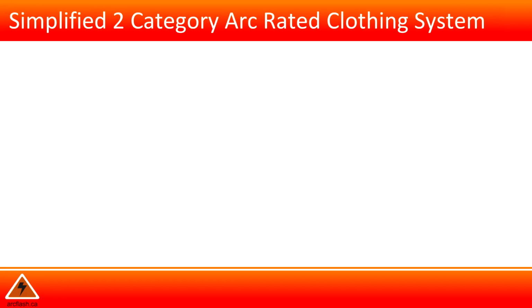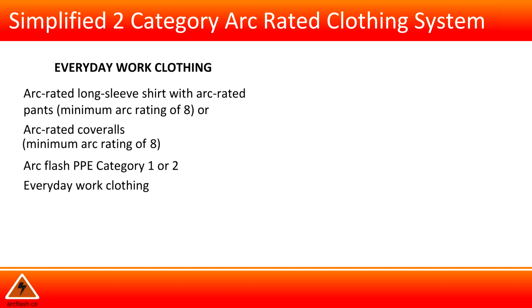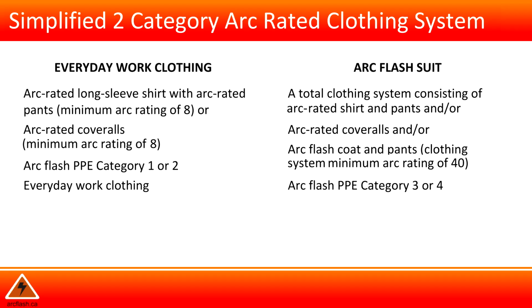There is a simplified 2-category arc-rated clothing system. An everyday work clothing system consisting of arc-rated long-sleeve shirt with arc-rated pants or arc-rated coveralls, with a minimum arc rating of 8 calories per centimeter squared. This will satisfy Arc Flash PPE Category 1 or 2 type tasks. And then there is an arc flash suit, a total clothing system consisting of arc-rated shirt and pants, and or arc-rated coveralls, or arc-rated coat and pants, with a clothing system minimum arc rating of 40 calories per centimeter squared. This will satisfy Arc Flash PPE Category 3 or 4 tasks.